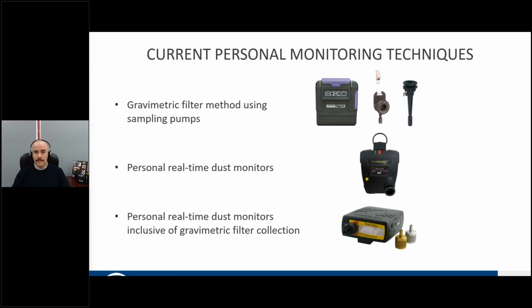It is the gold standard. We have it sent to the lab for analysis, so you can look at things like your respirable dust levels, and also the concentration of contaminants of concern like RCS or diesel particulate matter. Again, it's a tried and tested, long-standing range of instrumentation. The pump provides a flow rate very accurately over your filter sampling train, and you're able to determine what that worker has been exposed to, or if you're getting migration of the boundary, for example what fibers are migrating from the boundary of your site.